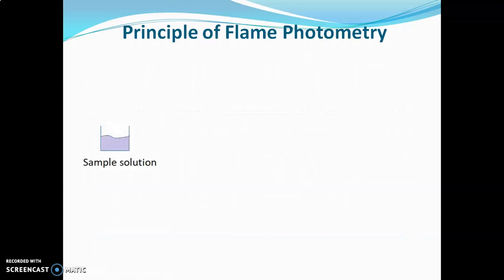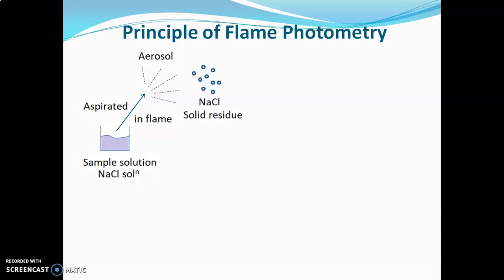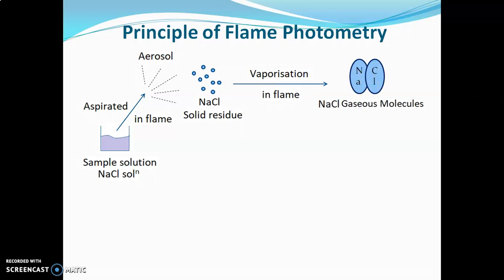Now we will see the same thing diagrammatically with an example using sodium chloride. A NaCl solution is aspirated into the flame, producing droplets. Due to the flame temperature, the solvent evaporates and a solid residue of NaCl remains in the flame. This solid NaCl then vaporizes, producing gaseous NaCl molecules, which then undergo thermal dissociation due to the flame temperature.